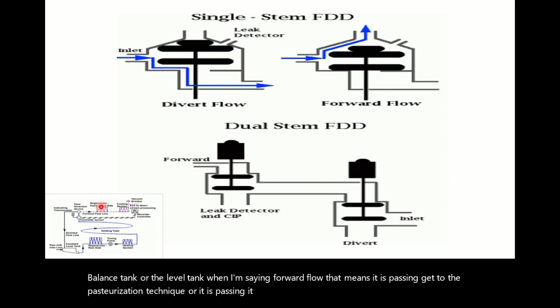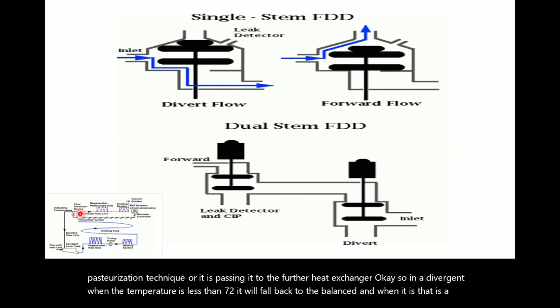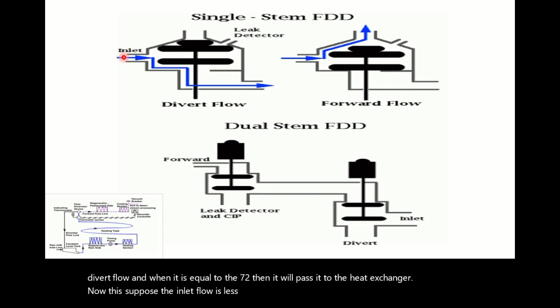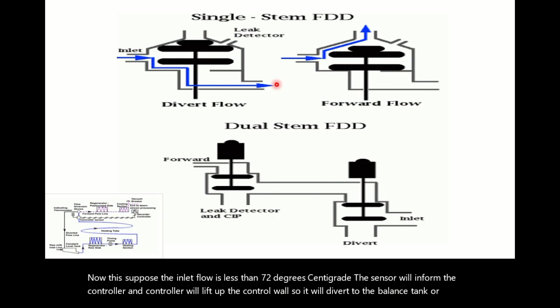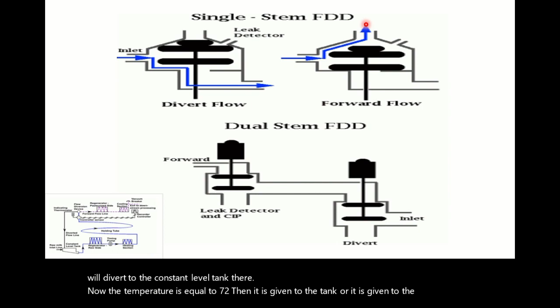So in a divert, when the temperature is less than 72, it will fall back to the balance tank. And when it is equal to 72, then it will pass to the heat exchanger. Suppose the inlet flow is less than 72 degrees centigrade, the sensor will inform the controller and the controller will lift up the control valve, so it will divert to the balance tank, the constant level tank. Now when the temperature is equal to 72, it is given to the heat exchanger, where my temperature is going to reduce to 7 to 9 degrees centigrade.